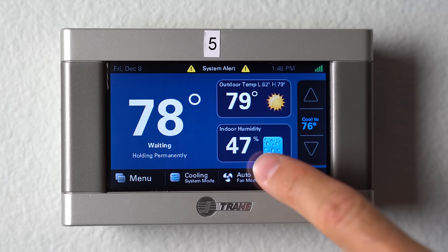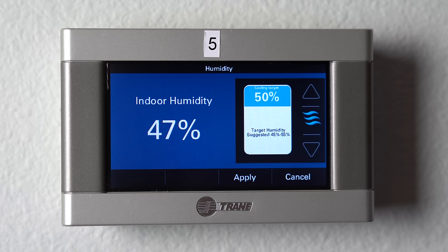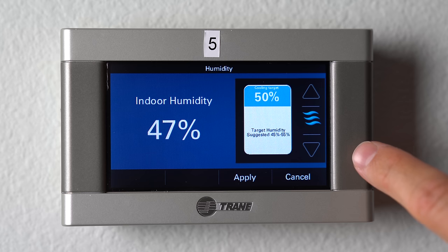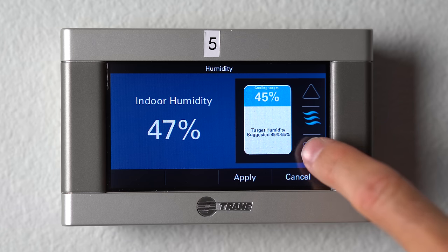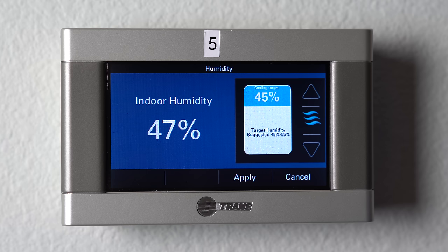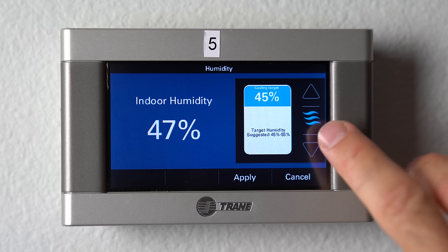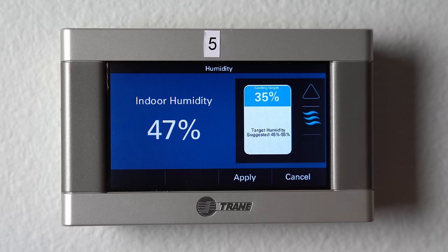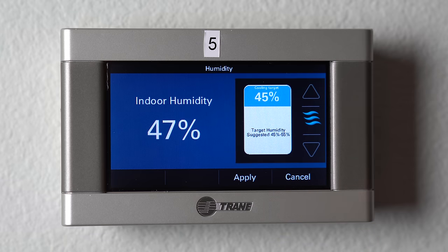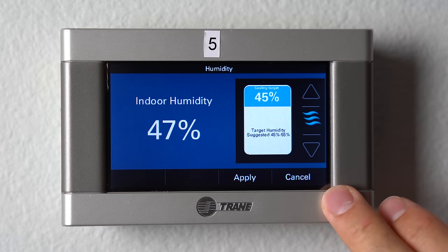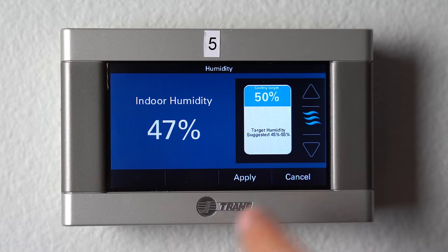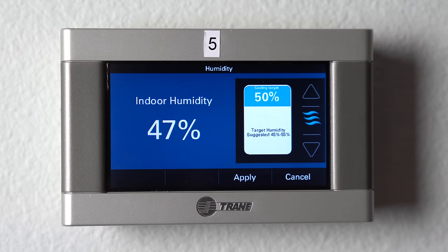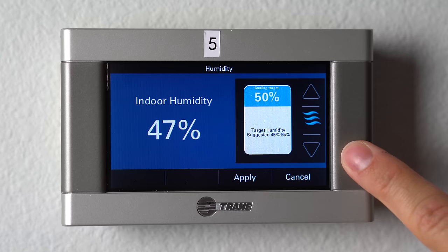To control the humidity, you can go ahead and click right here on the indoor humidity — this is what it's reading. This Trane thermostat allows you to select different target humidities; it runs the system a little bit past set point to dehumidify extra. You can go all the way down to 35%, though 45 to 55 is usually perfect. We leave ours at 50% in our office. You can click this and bring up the target humidity right here.